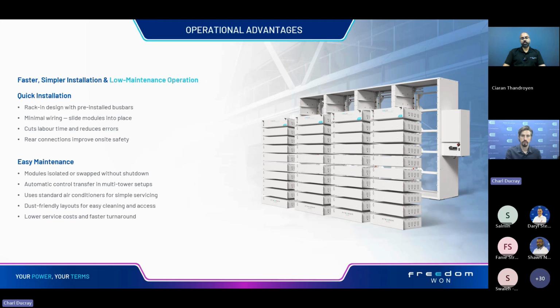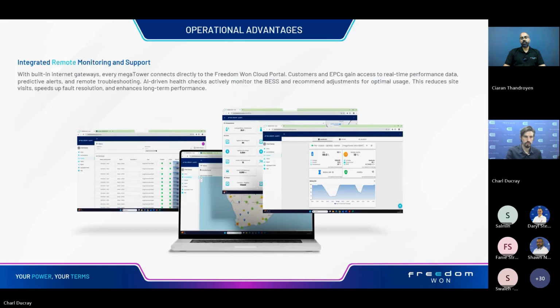Awesome. And then just the last thing on the actual battery modules themselves. What's made this possible is those clip-on connectors at the back. Yeah, so we have connectors that have leaves that can shift side to side, which allows for easier push-in connection of the bus bars themselves. So there is no termination of bus bars on the modules. You slide them in place and they join directly onto the bus bars. And then lastly, just on the operational side, each battery module has an integrated remote gateway.